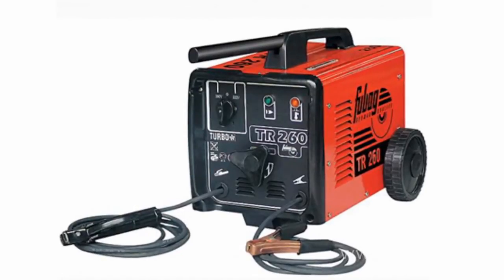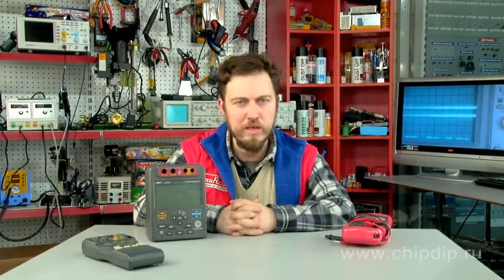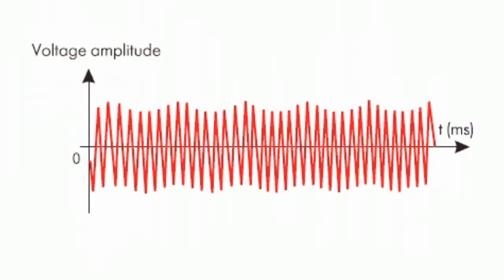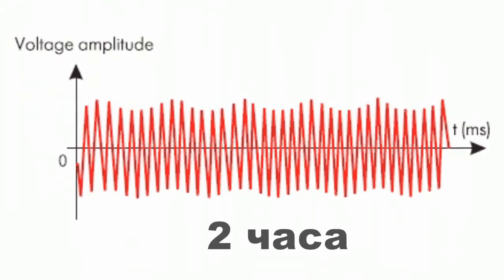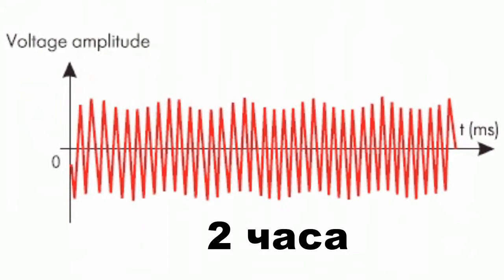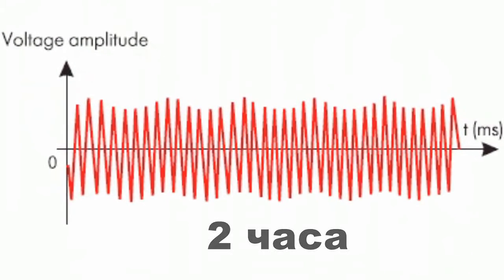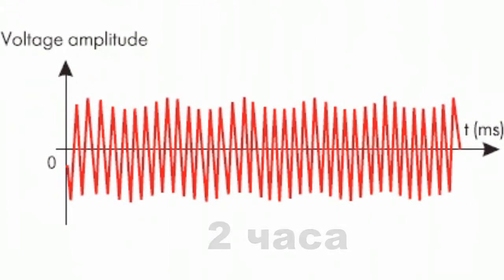or if the loads have a long or changeable operation cycle, the interference should be observed for a longer period of time. The measuring time may be increased to two hours. It must correspond to the operating cycle of the load and all the time necessary for the observer to perceive the long-term flicker effect.